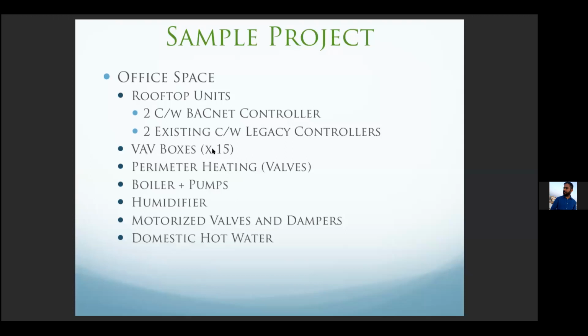VAV boxes. Now, each VAV box is going to need its own controller. Technically, so does perimeter heating, but what may happen is if it is being used as supplementary with the VAV boxes, it is going to be in the same zone. So we may be able to use one point on the VAV box to send a command to the perimeter heating valves to open up or close up, depending on what we need to do in the space.